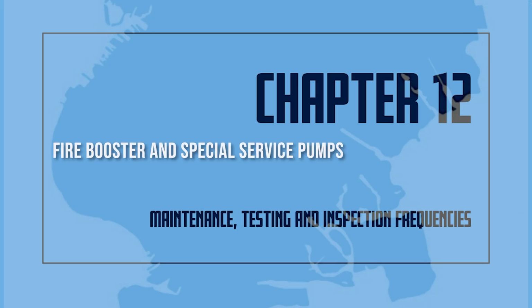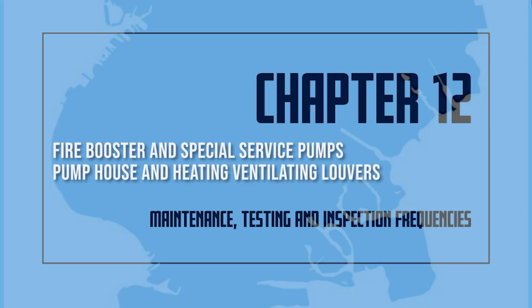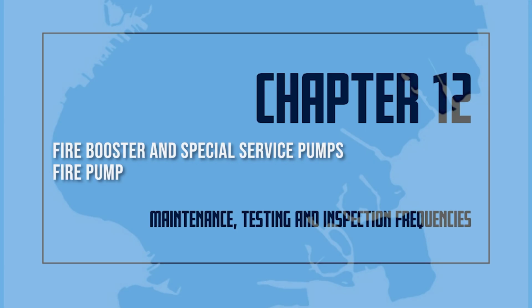B. Fire booster and special service pumps. Pump house and heating ventilating louvers. A visual inspection shall be performed weekly to ensure that the heat is not less than 40 degrees Fahrenheit and not less than 70 degrees Fahrenheit for pump rooms with diesel pumps without engine heaters, and that ventilating louvers are free to operate.